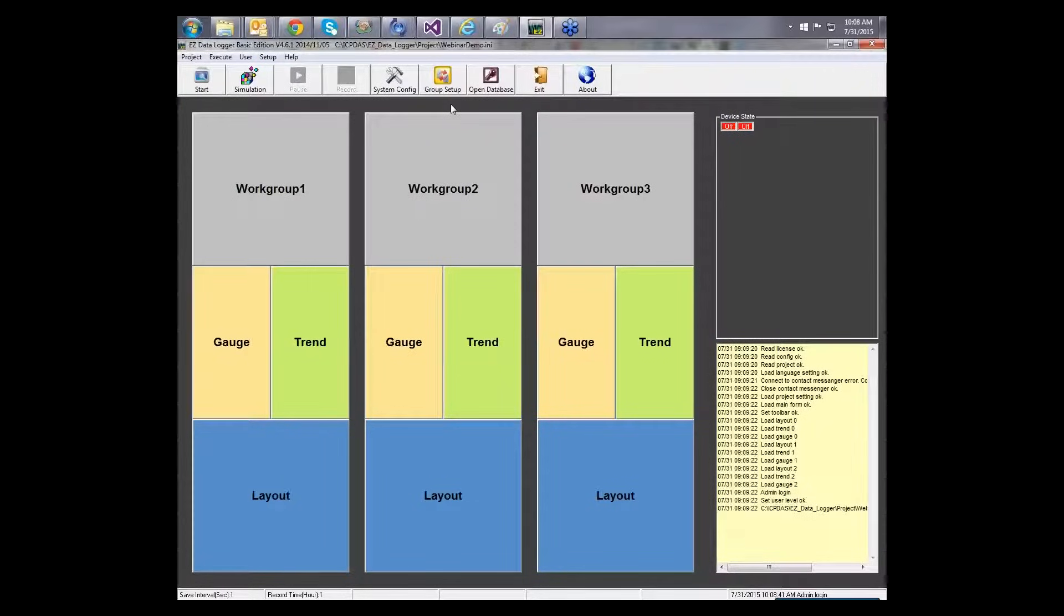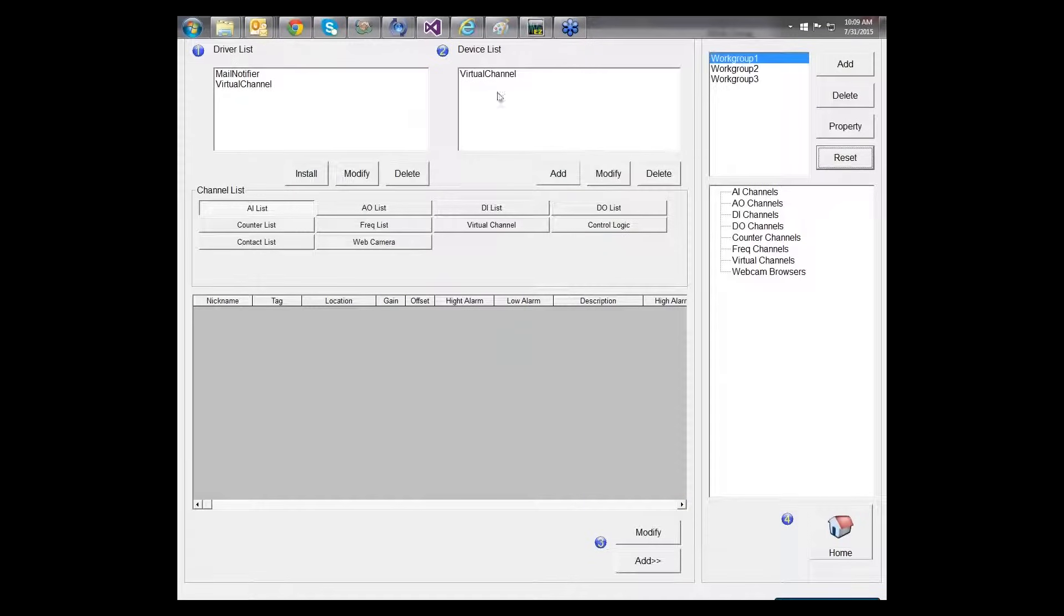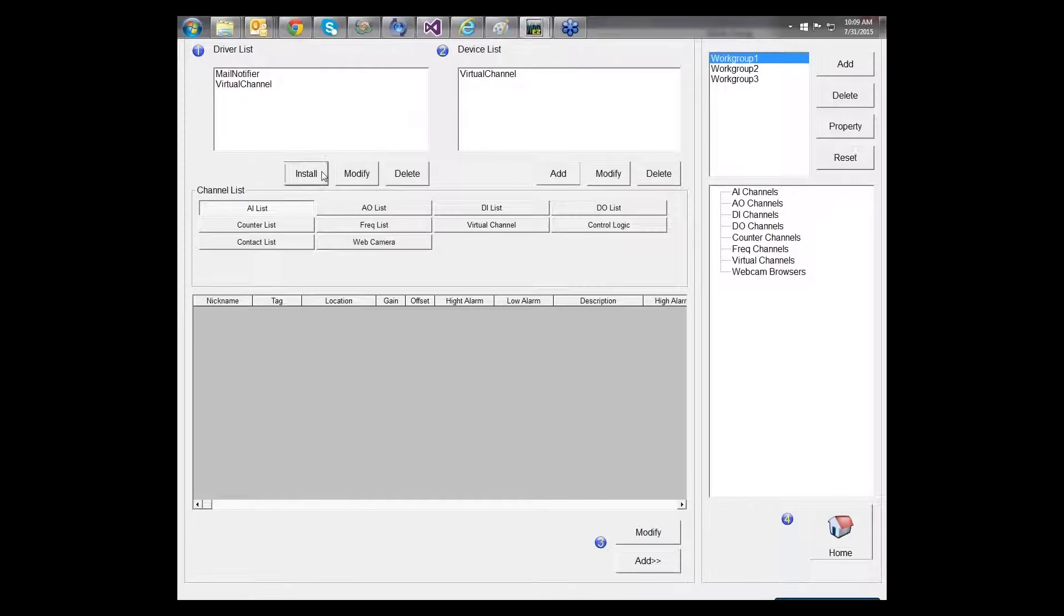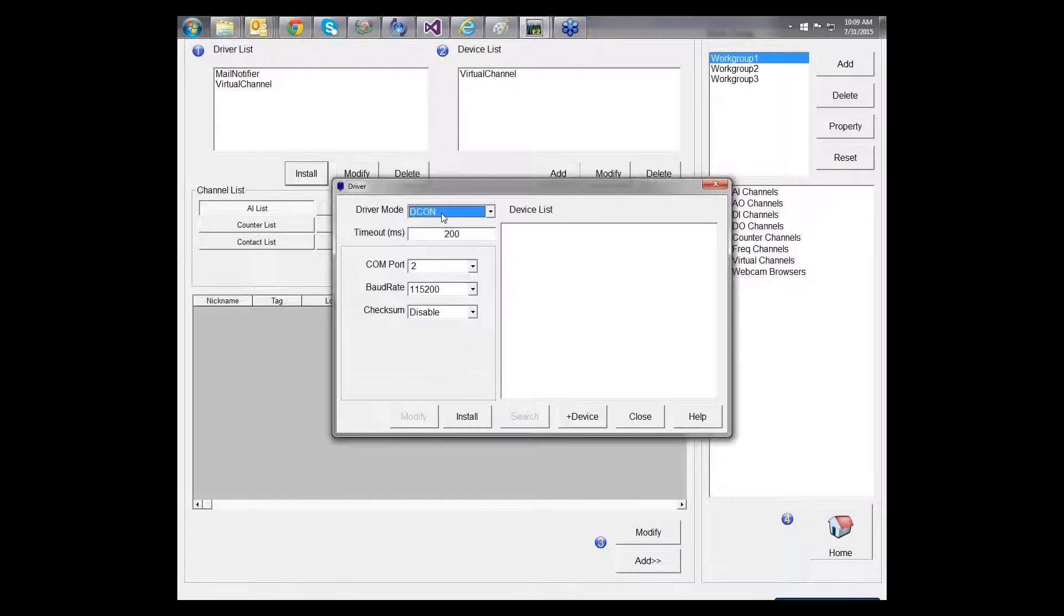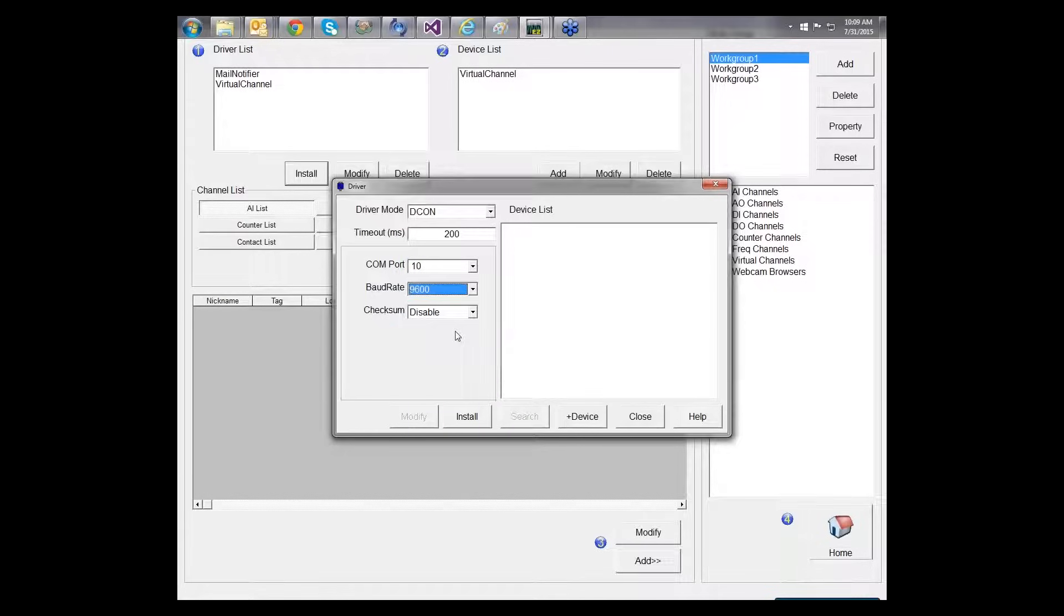Then, we need to set up our modules here, which I would like to tell you first what I'm using. I'm using one i7060, and also I have one 7561, which is a converter from 485 to USB. So, we're clicking on a group setup. First step is setting up the driver. So, we are clicking on the install and click on the DCON protocol, which is i7000 series. And my com port is 10, which I already know. The baud rate is 9600. And the checksum, then we are clicking on install. You will see that we created the driver here.